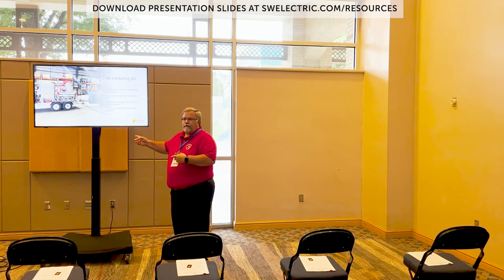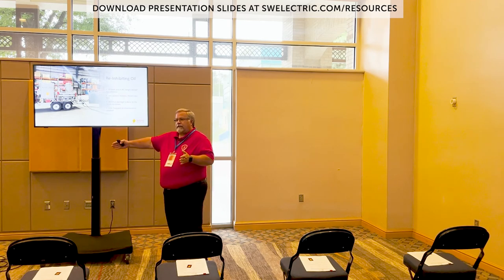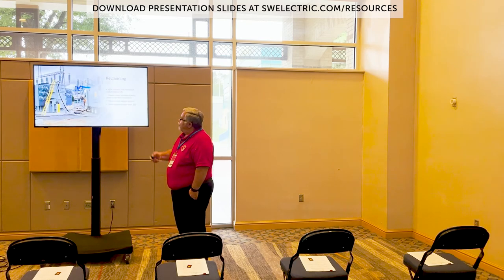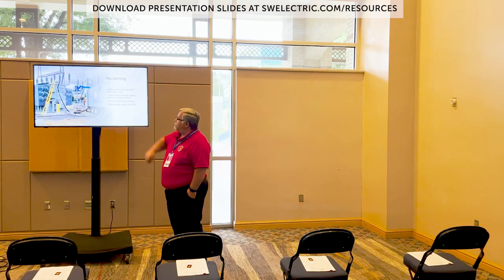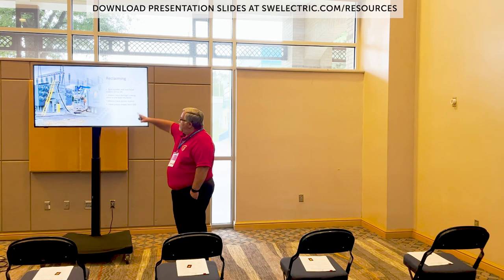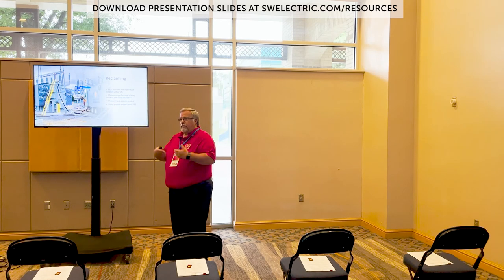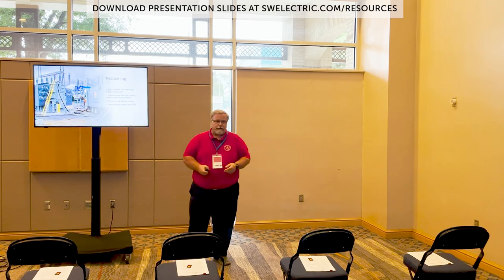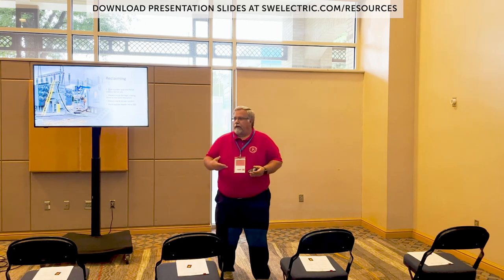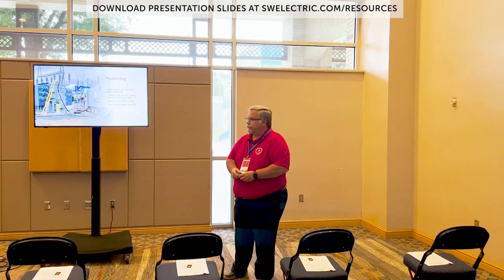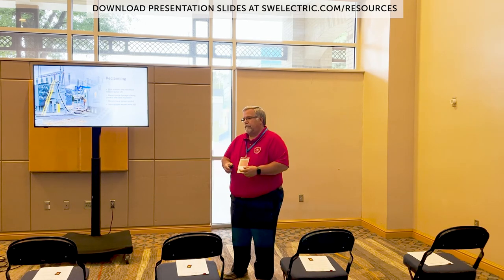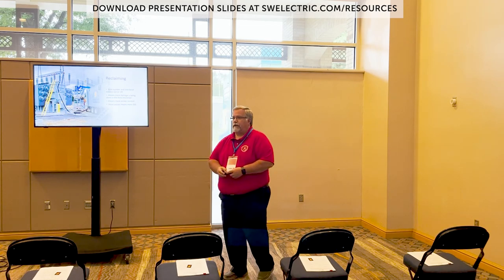This is the best time for you to do this maintenance, because believe it or not, it's going to be a cheaper time to do it, and you're going to extend the life of the transformer a lot more than if you wait until your test results go questionable and unacceptable. Because then we have to do more passes, which increases your bill, and we might have to do it, say, 5 years later instead of 10 years later on the re-inhibitor.